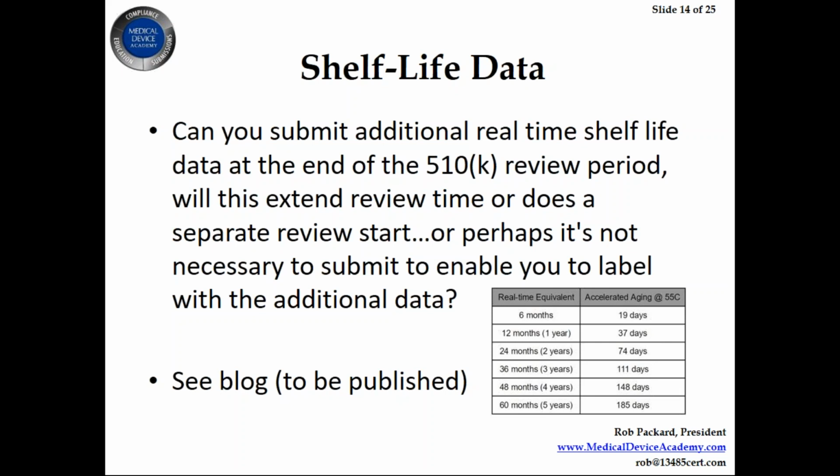So if you're trying for 5 years, pick something that's 2, 2.5, 3 years, just in case you fail the 5-year time point. And you'll have the result for 5 years accelerated before you'll have 1 year of real-time done, so you can adjust your protocol for the real-time aging to match up with what passed for accelerated aging later and not have to restart the whole entire experiment.